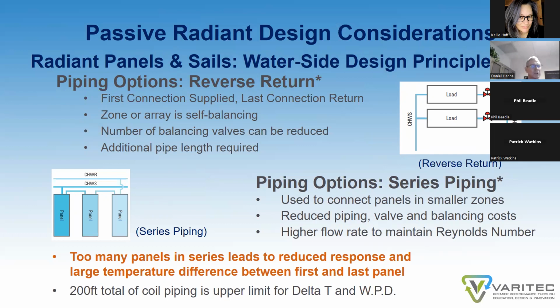Another piping solution is series piping, but you have to be very careful about series piping because the furthest device from the entering water is going to have the least capacity, as that chill water is absorbing the energy of that space. So there may be an application for it because it has some advantages in specific environments, but realize the total capacity loss throughout that array in a series configuration.